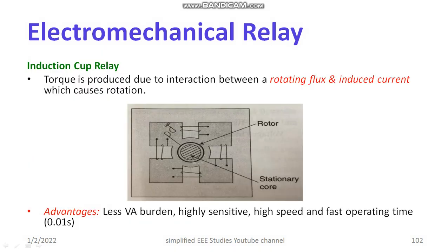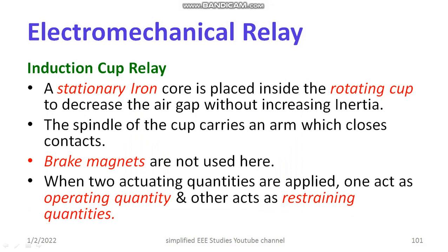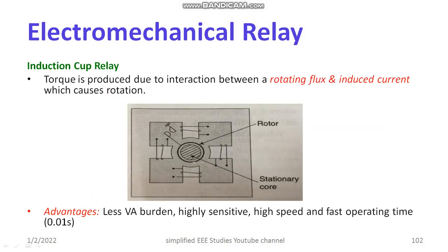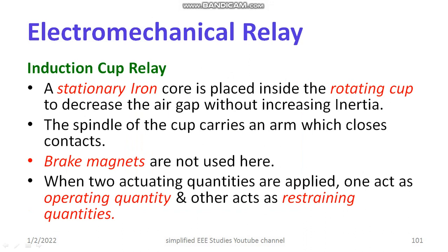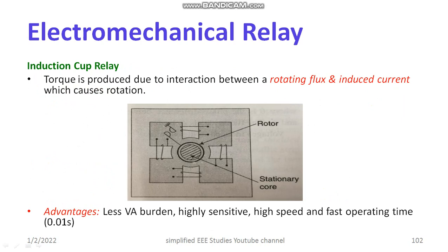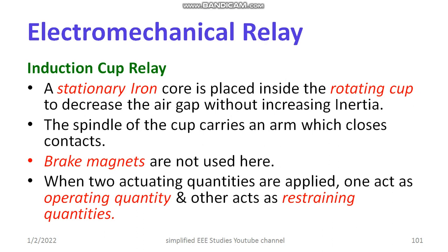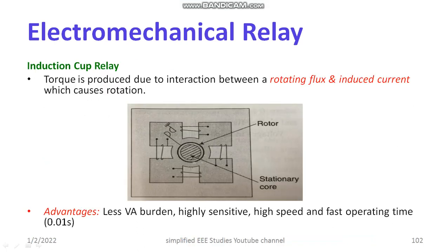This is your stationary core, and you can see the rotor part. There are no brake magnets enclosed here. When two actuating quantities are applied, one acts as the operating quantity and another acts as the restraining quantity. The torque is produced due to interaction between the rotating flux and the induced current, which causes rotation. The advantages of induction cup relay are less VA burden, high sensitivity, and high speed of operation compared to other types of induction relay.